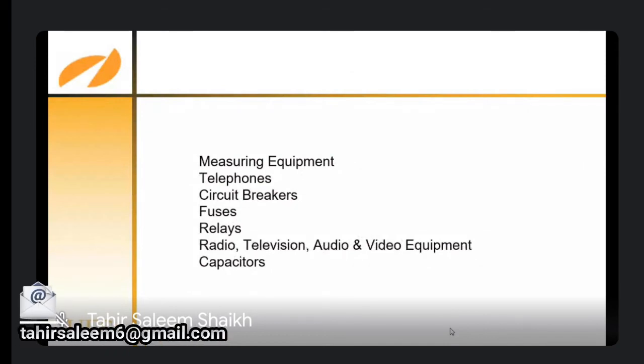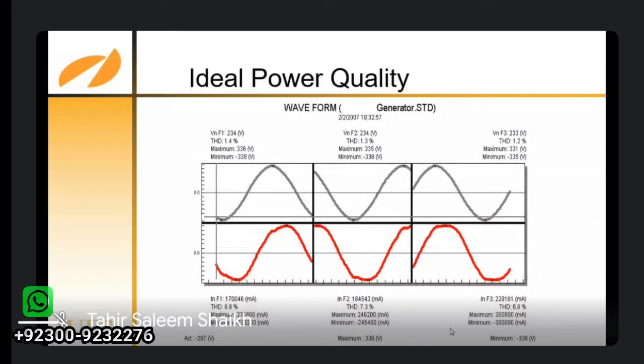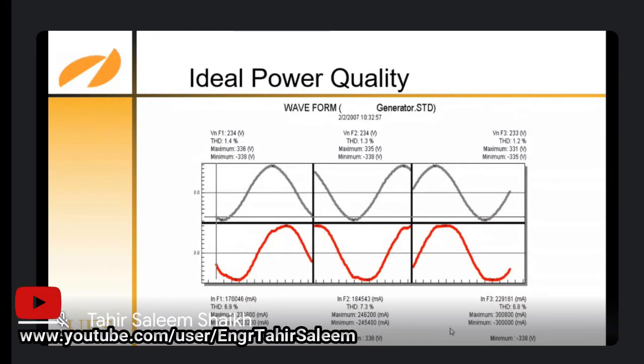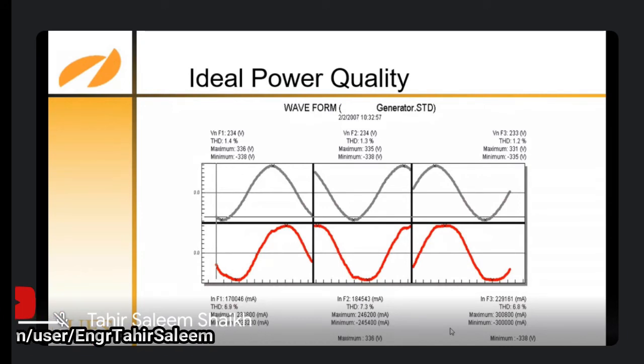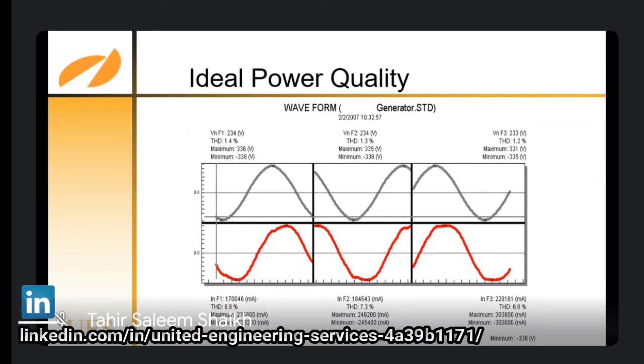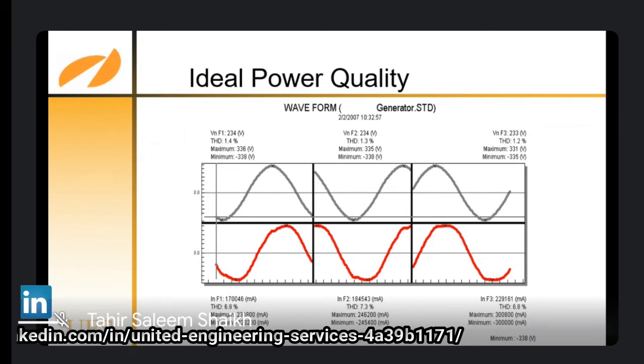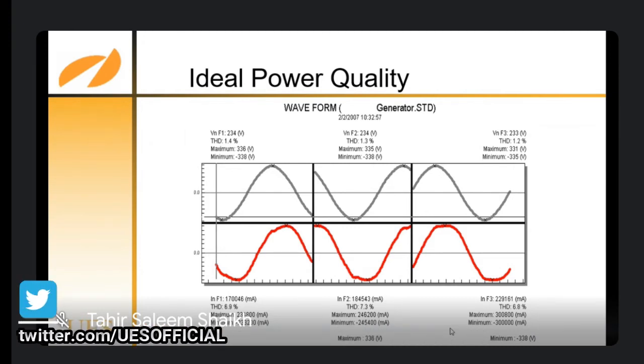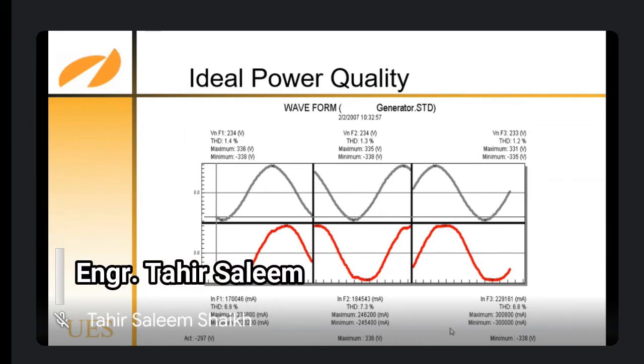Measuring equipment, telephones, circuit breakers, fuses, relays, all will misoperate. Now this is a reading taken by us with a harmonic analyzer, which gives you an ideal waveform. In this case, the total harmonic distortion is 1.4% on one phase, 1.3% on another phase, and 1.2%. So according to your requirement, you have to determine the THD levels as per IEEE or IEC standards. The current harmonics are 6.9%, 7.3%, and 6.8%. This is an ideal power quality.